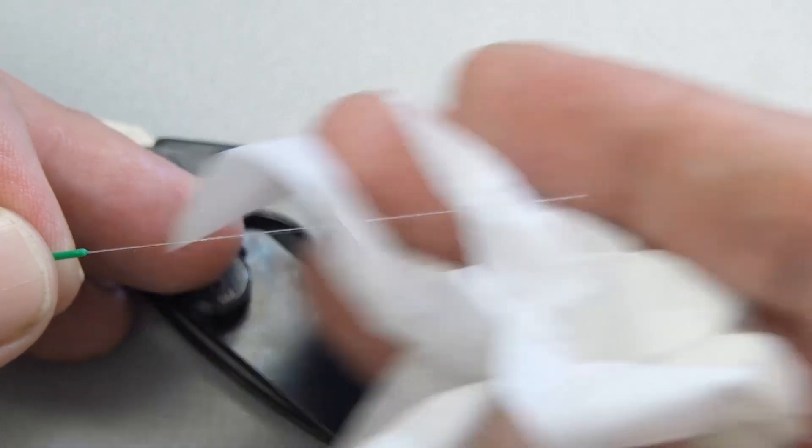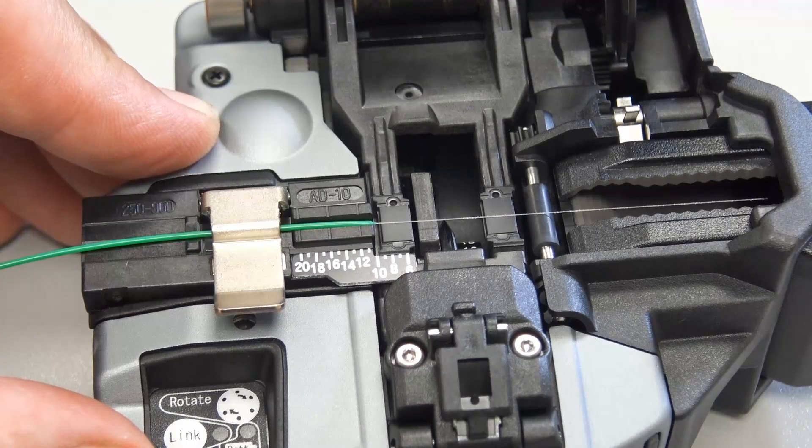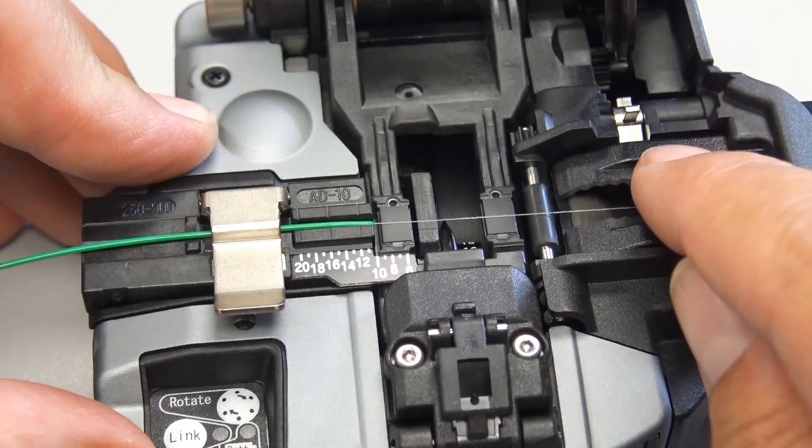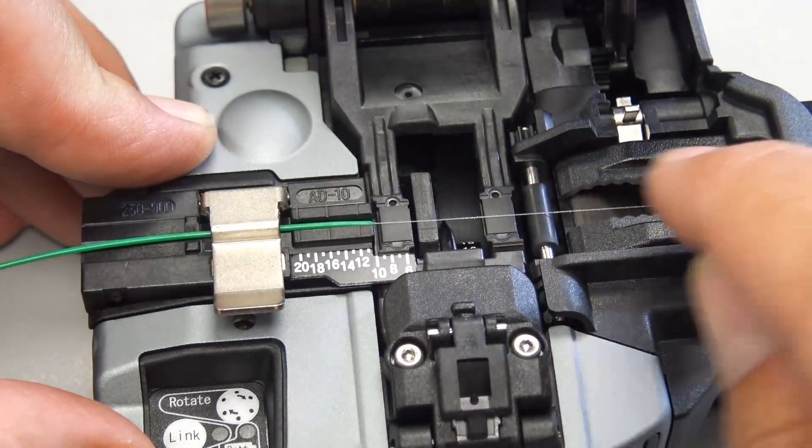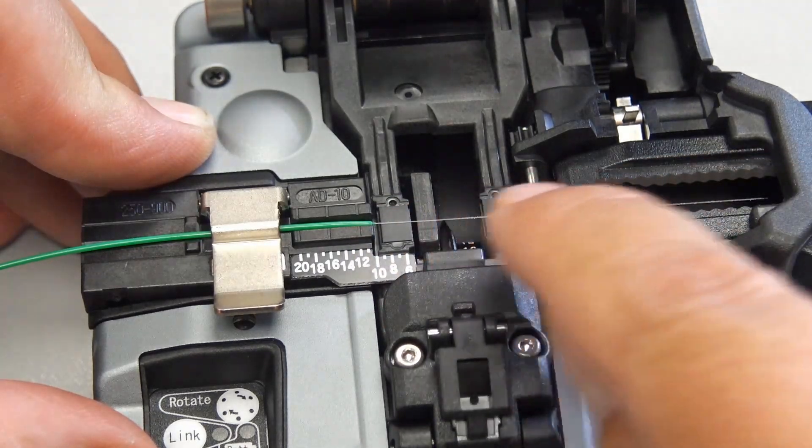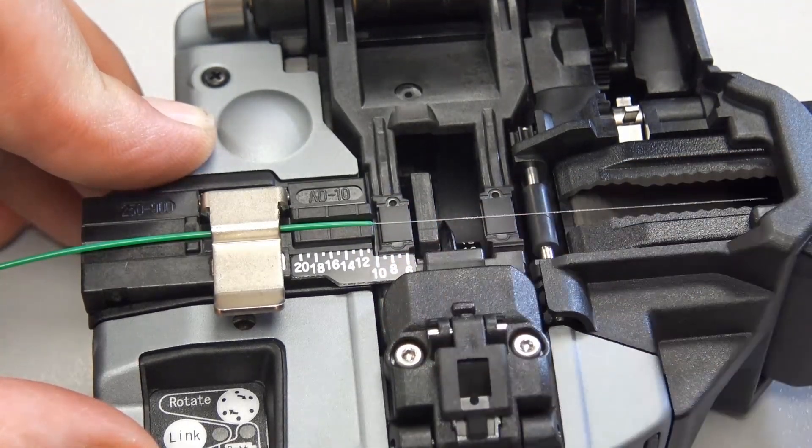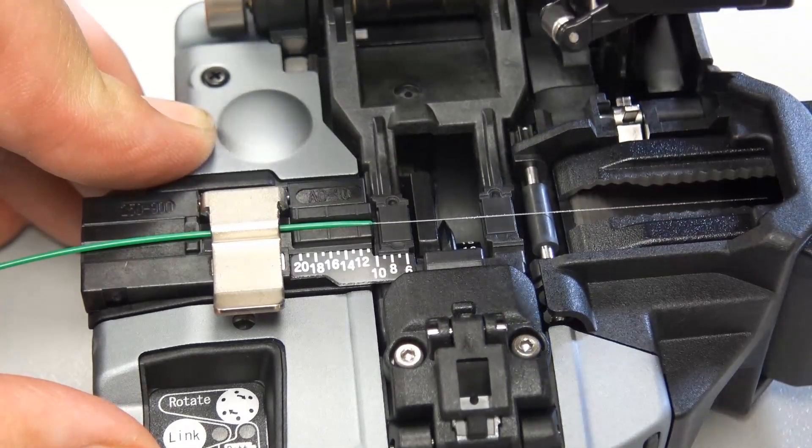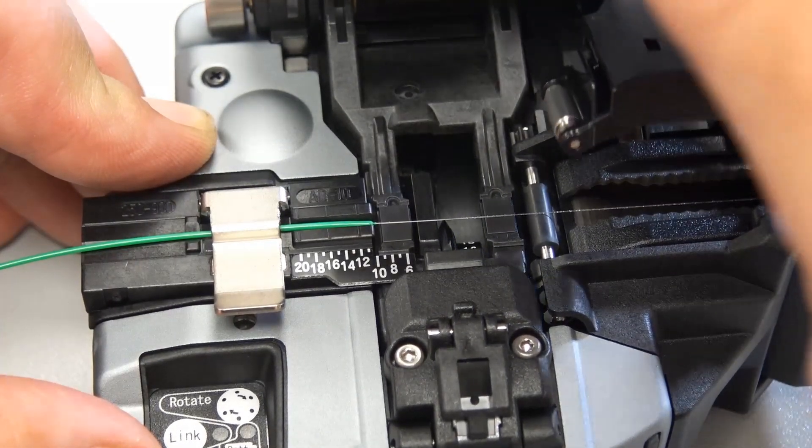We're going to cleave it at the 10 and a half mark. One thing I do want to mention: if you don't strip it properly, you might want to go over it a second time just in case there's acrylic material on there. If it's not taken off properly, when you go to cleave, you're going to think there's something wrong with your cleaver, but it's that material.